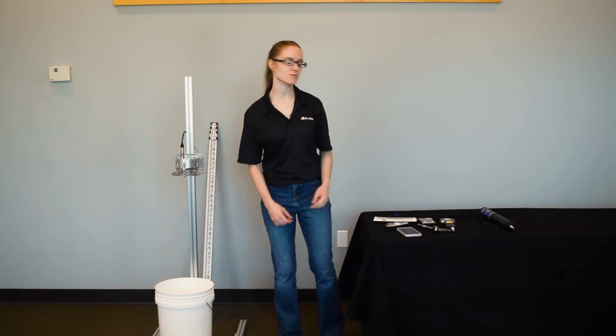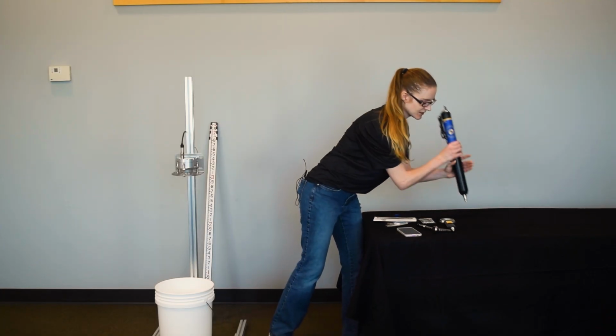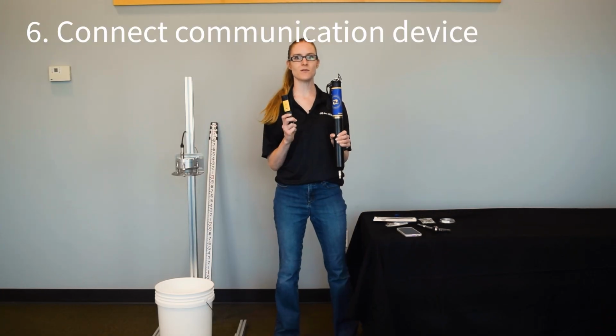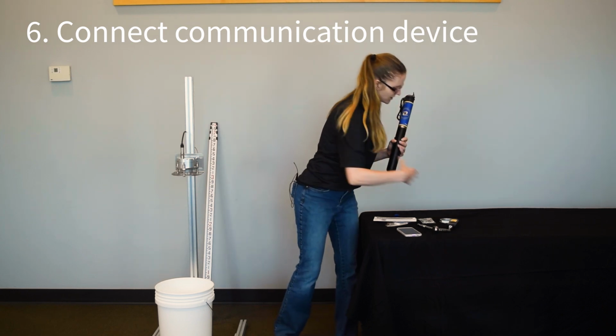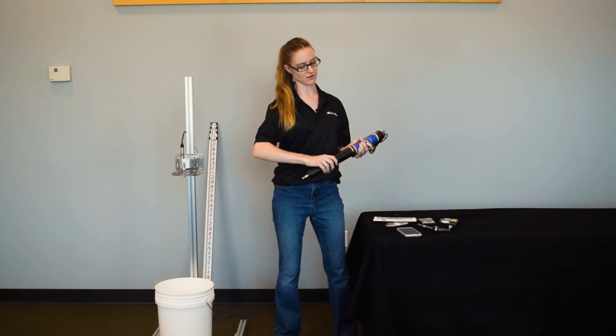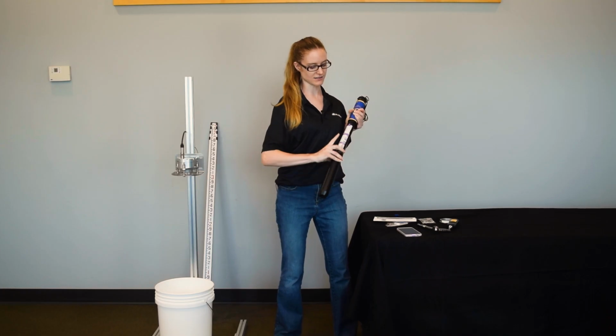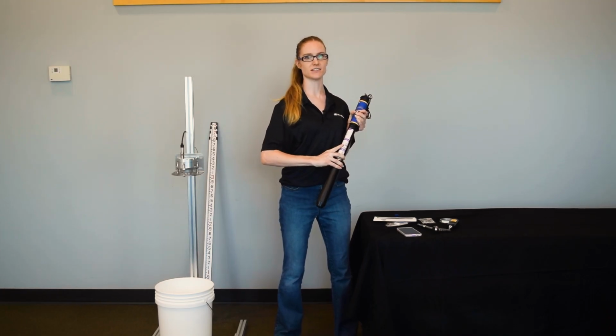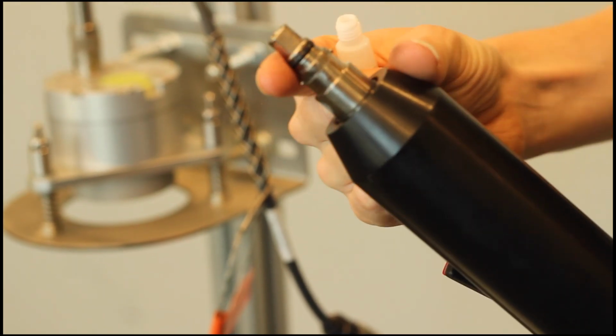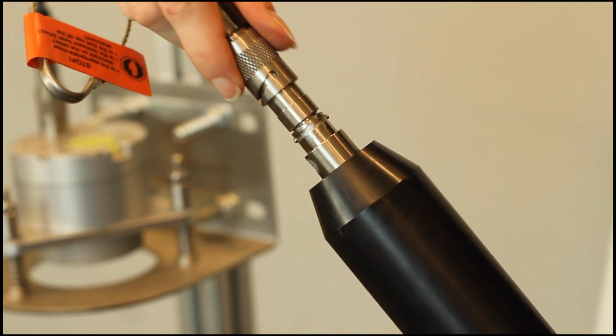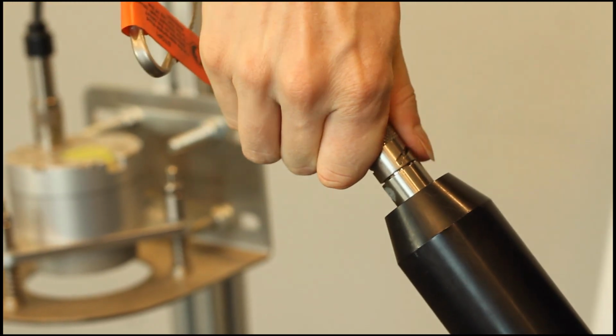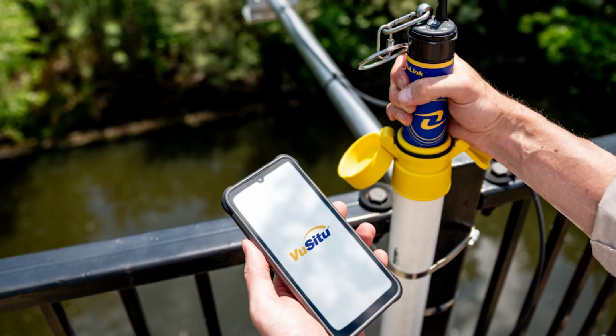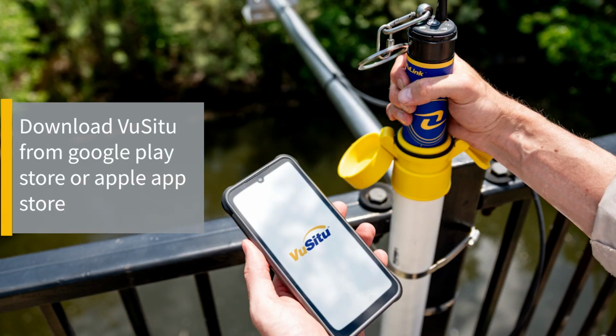To connect to the VuSitu mobile app, you'll need a communication device, like a VuLink or a TrollCom Plus. If you're using VuLink, you'll need to make sure that you install lithium manganese dioxide batteries. I've pre-installed some for the sake of this video. Connect the cable to the communication device the same way you did for the instrument, and turn the communication device on. Open the VuSitu mobile app on your mobile device. You can download VuSitu from the Google Play Store or the Apple App Store.